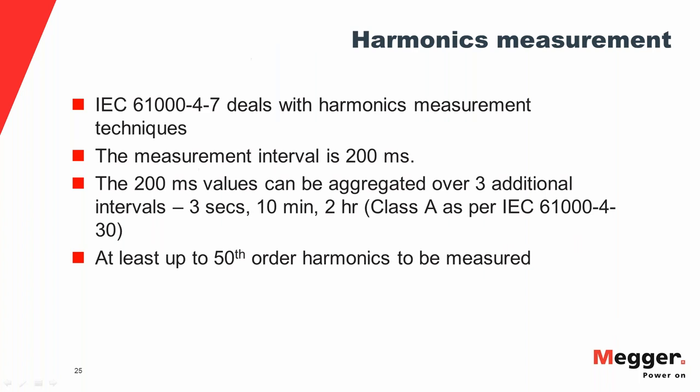Harmonics measurement is governed by IEC 61000-4-7. The measurement interval specified is 200 milliseconds, corresponding to 10 cycles in a 50 Hz system or 12 cycles in a 60 Hz system. These 200 ms values can then be aggregated over longer intervals — three seconds, 10 minutes, or two hours — for Class A instruments. Class A has the most stringent requirements. The standard also specifies that at least up to the 50th order harmonic must be measured.